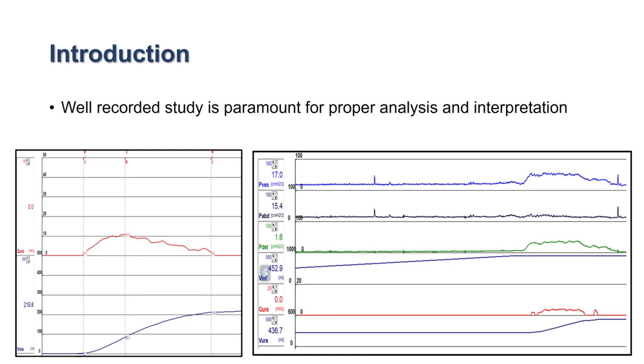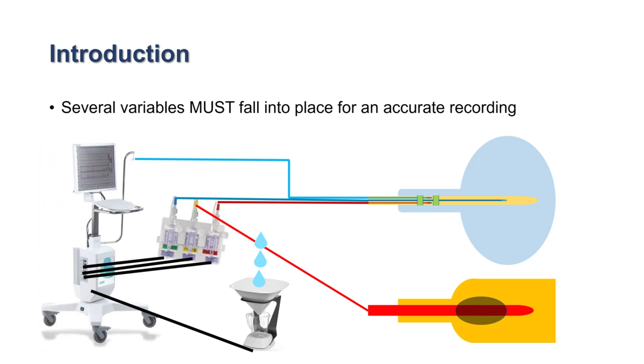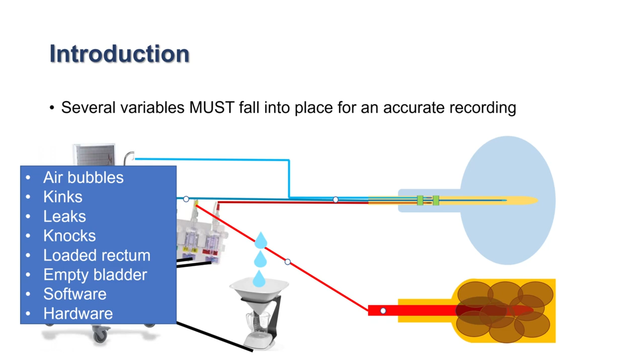Obviously, many variables must fall into place for an accurate recording, be it catheters, their connections, the transducers' connection with the computer, or the computer software's functionality. Many things like air bubbles, kinks, leaks, knocking, that is touching the transducers, a loaded rectum, an empty bladder, and software and hardware issues can lead to problems with interpretation and recording of urodynamics.